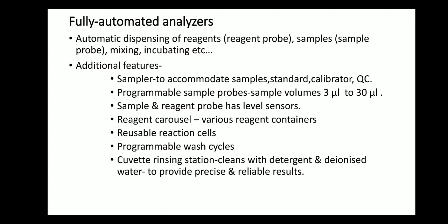Now coming to the fully auto analyzer. Here the dispensing of reagent and sample, mixing, incubating, everything is done by the auto analyzer. You have to just keep the sample required, that's all. Most investigations require a serum sample. A few tests might require a plasma sample. So based on that you have to just separate the sample and keep it, that's all.